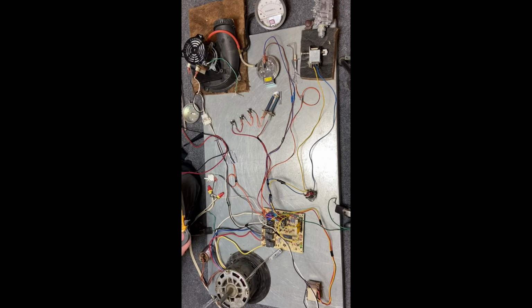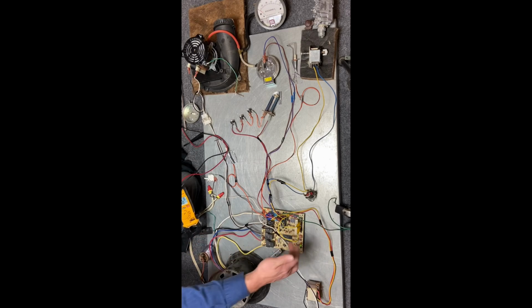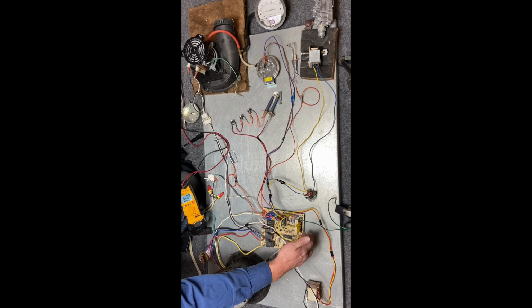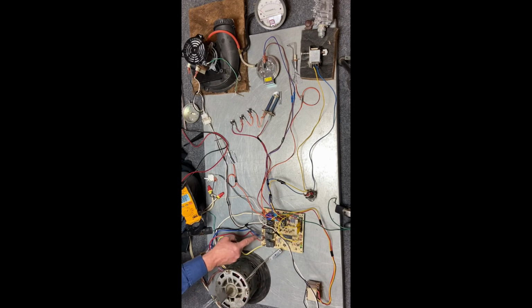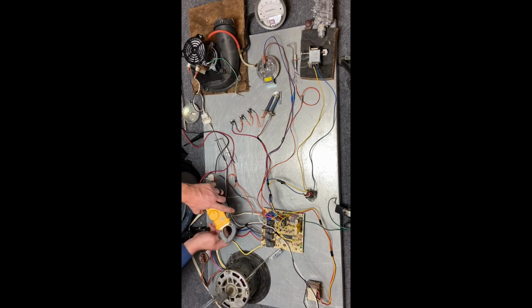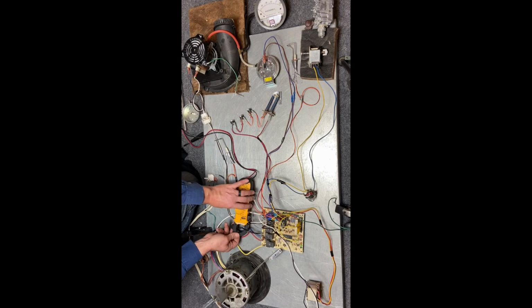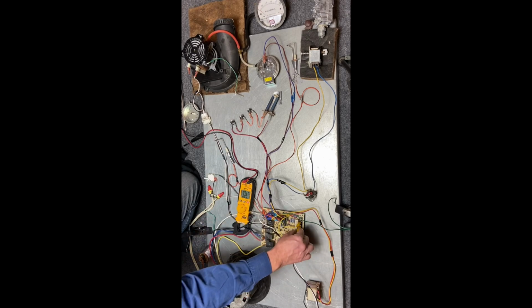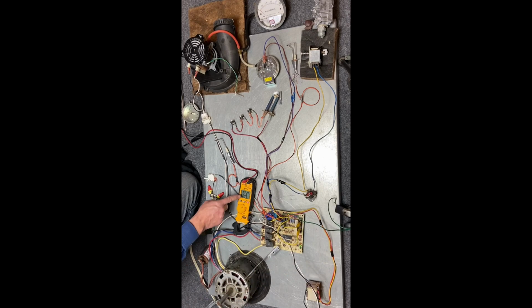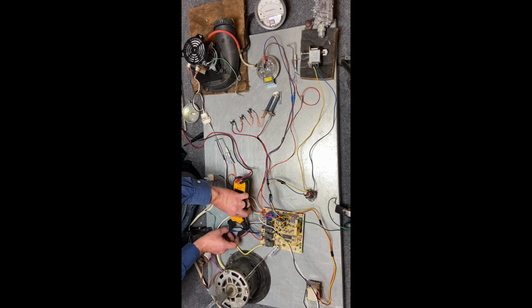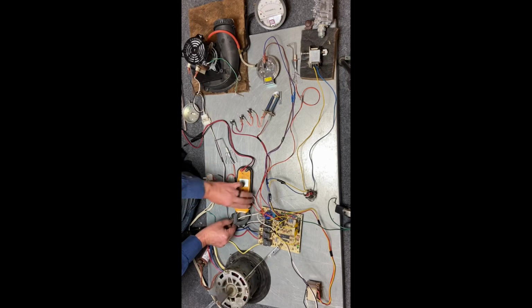So what we're going to do next is call for cooling. When I have the thermostat call for cooling, it's going to connect R to Y. Then we're going to energize the speed for cooling, which is going to be this relay, and it's going to energize high speed. So I'm going to clamp the meter around high speed, and right now we see that there's 0 amps. But when I connect R to Y, we hear a click, and here I'm pulling 5.6 amps. So I'm using more amps, a higher speed of the motor. And we also check the neutral side, and we see that there is also 5.6 amps.